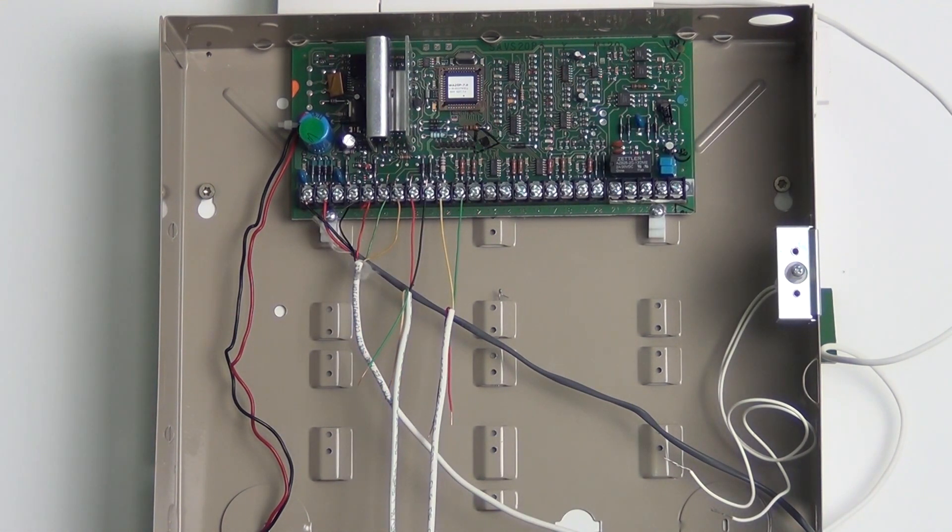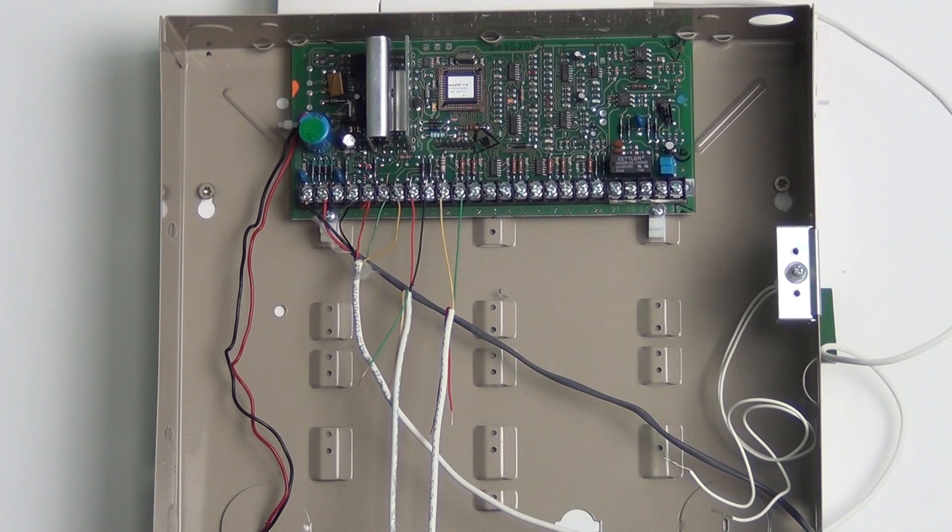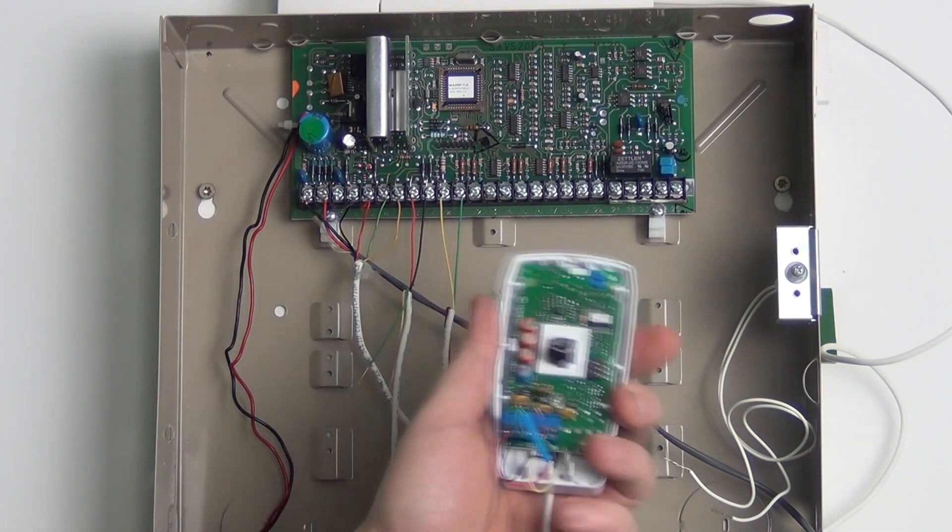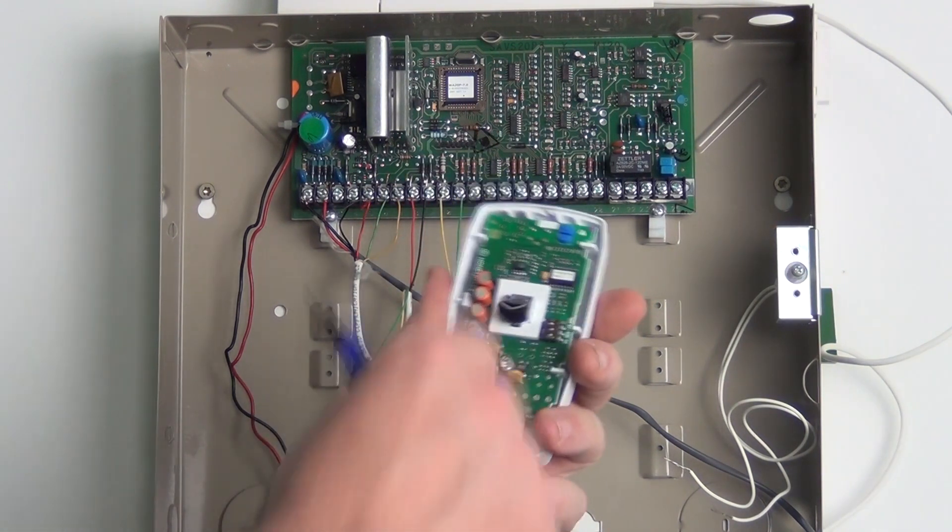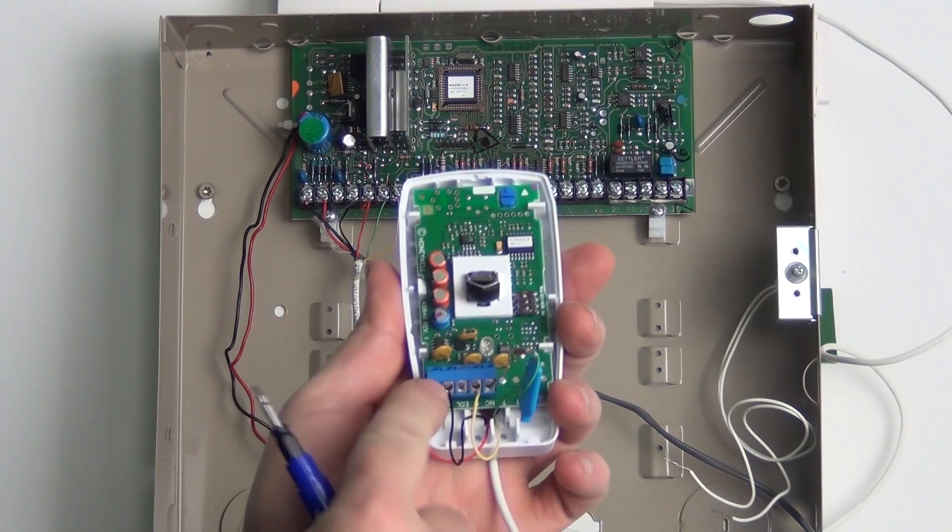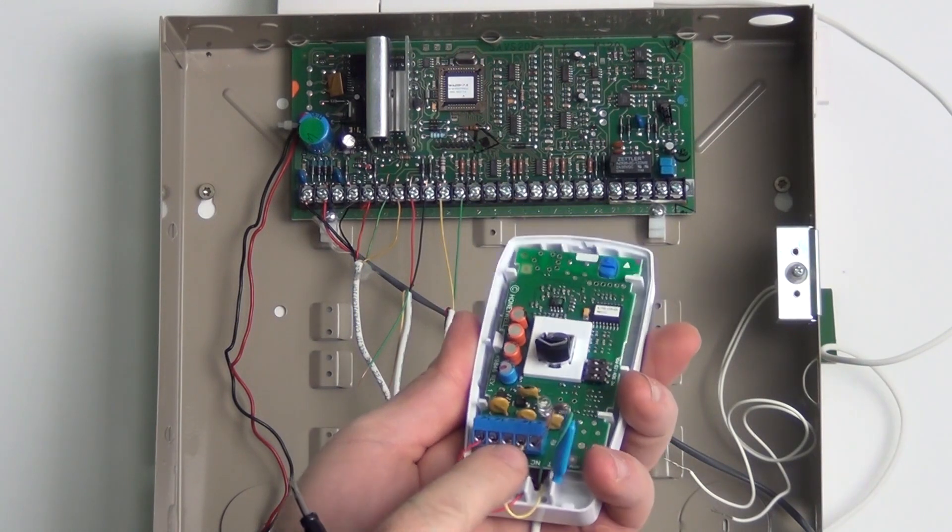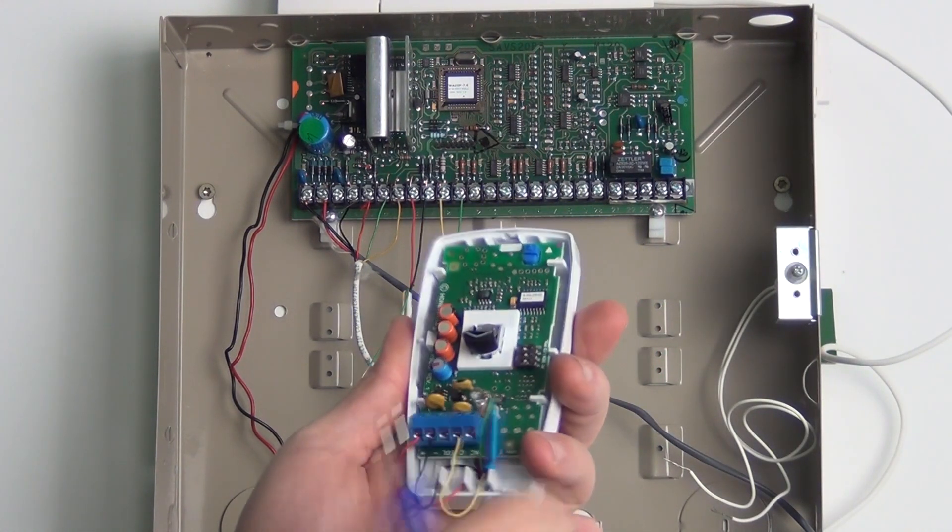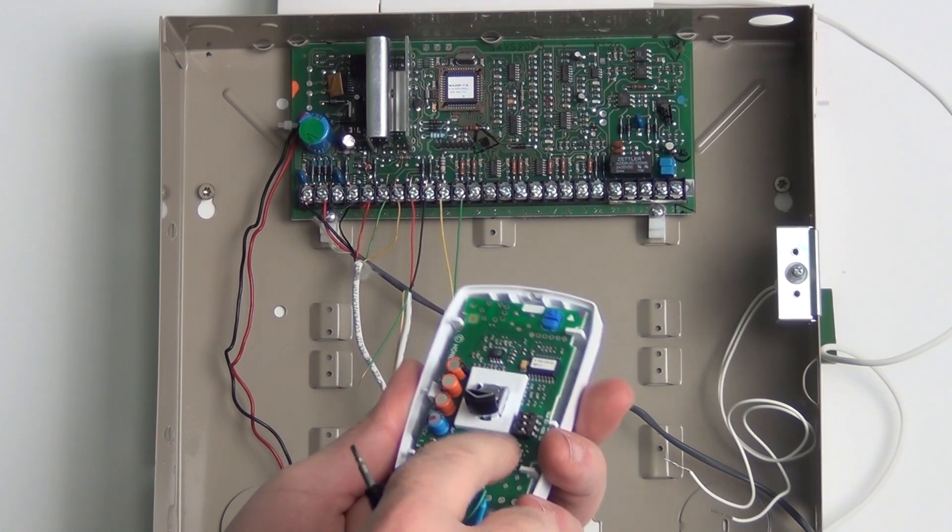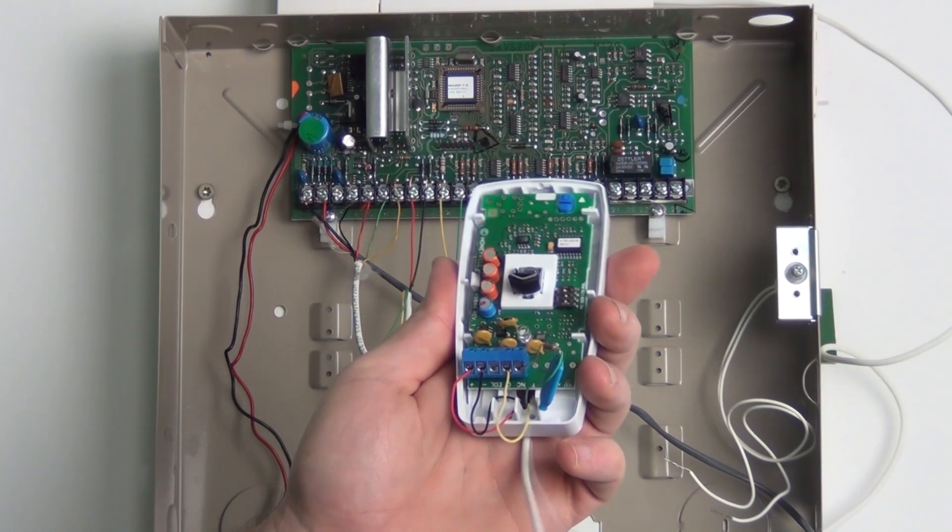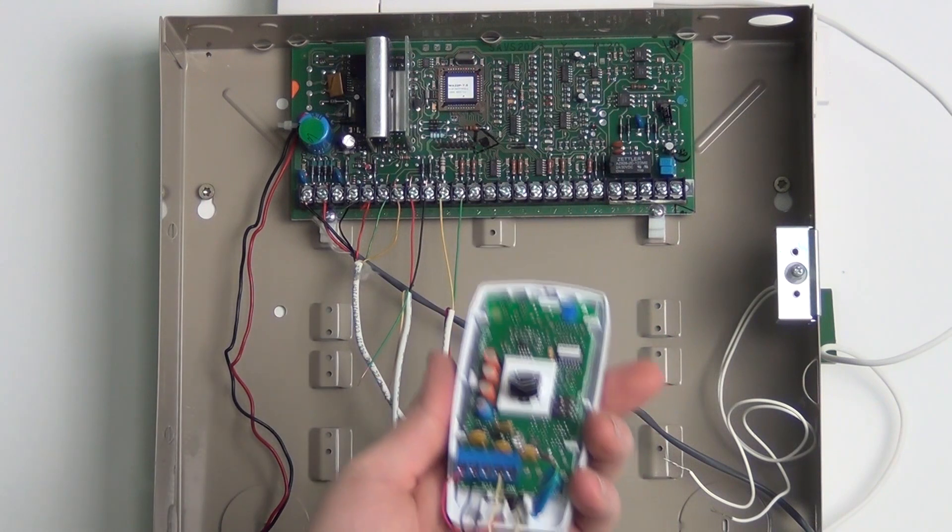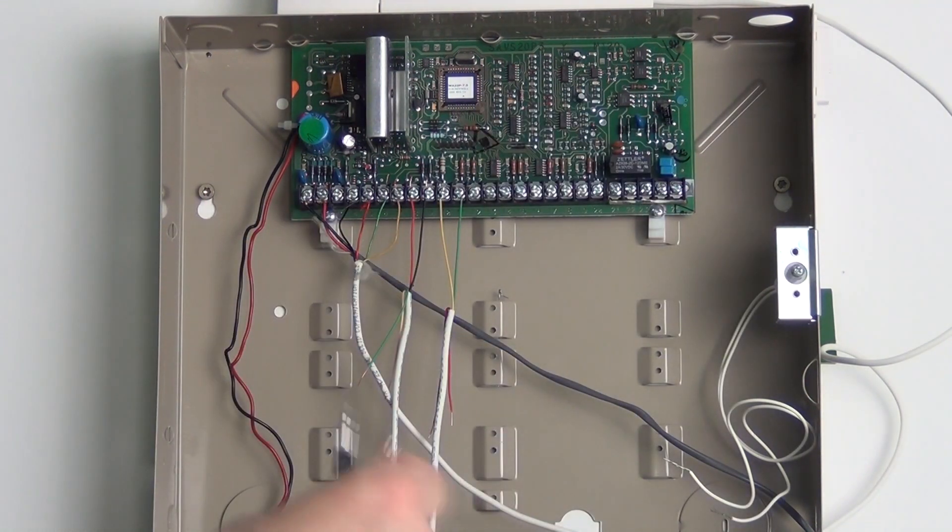The next one I am going to put in here is a powered device with 4 wires. This is an IS2535 from Honeywell. I've got the 2 power wires, the black and red, going to these 2 terminals inside. Then I've got the zone wires over here on the normally closed and common. On the normally closed terminal, the green wire, I have added my resistor in series with that one wire. So this is normally closed, so it will run in series with one of the wires.